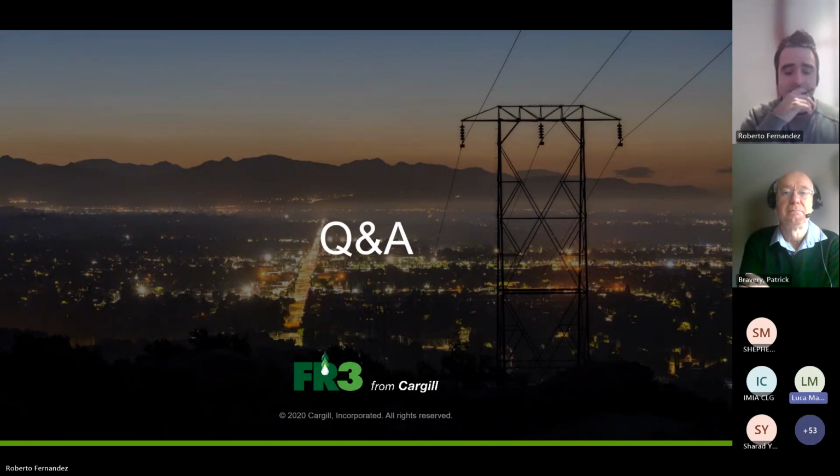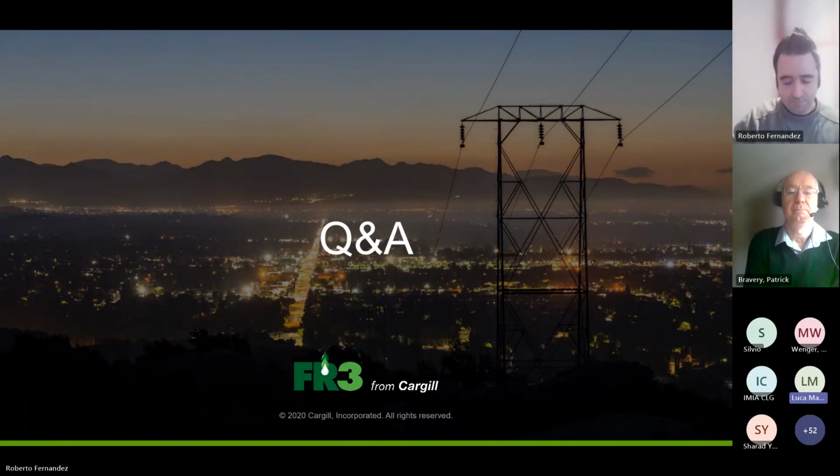So when we take into account the higher prices for the natural ester, we also need to consider in the proper way all the benefits mentioned by Roberto and how those really help in reducing the maintenance costs, the civil works costs, and so on. That will give us the full picture, which is the one we have to look at. And consider that the price and the value of the oil within the substation, within the electrical infrastructure, is very small compared to the other parts. So I would definitely recommend such an investment, because it's the easiest and fastest way to be consistent with the roadmap towards sustainability and efficiency.